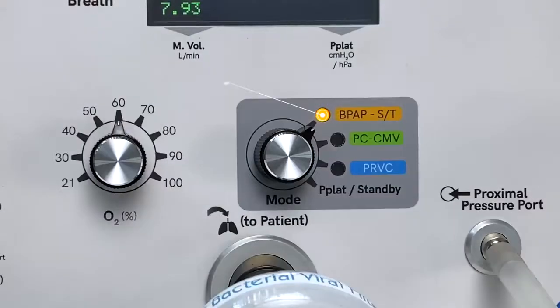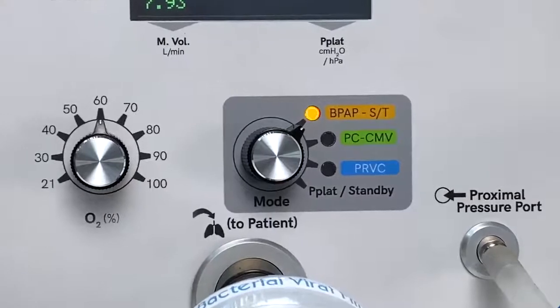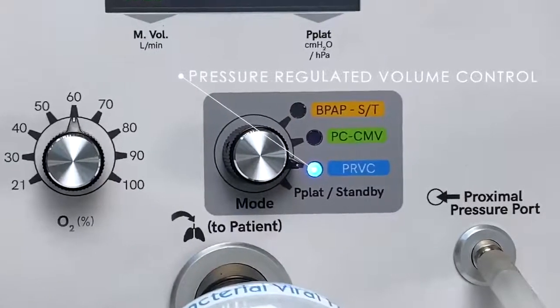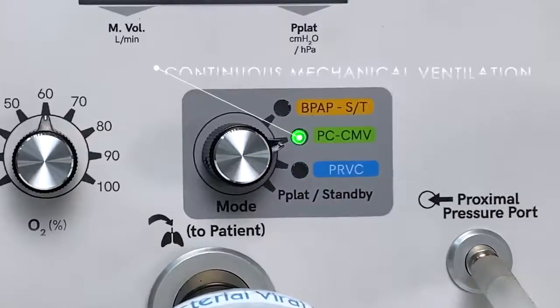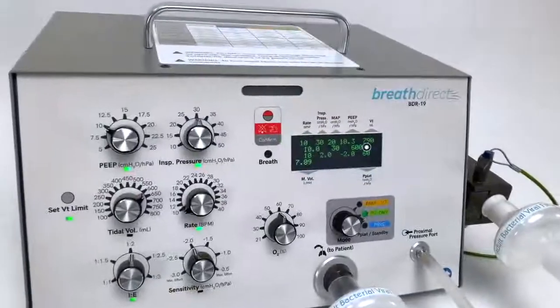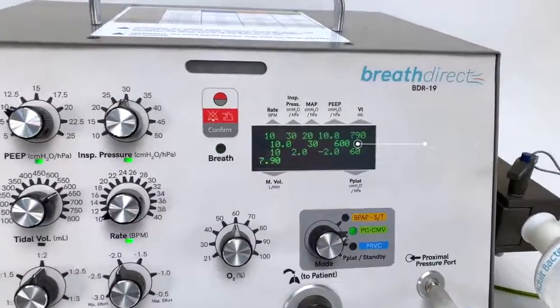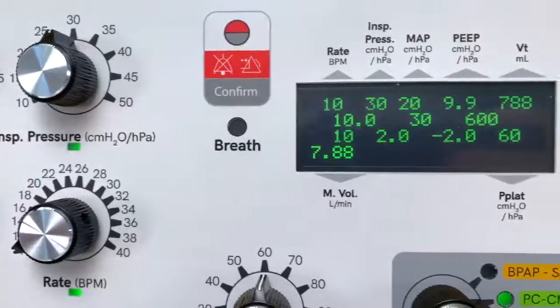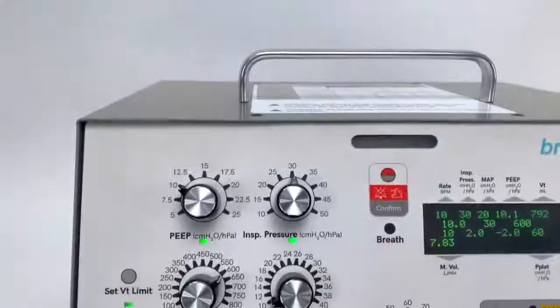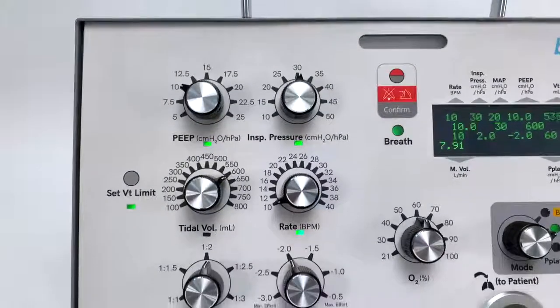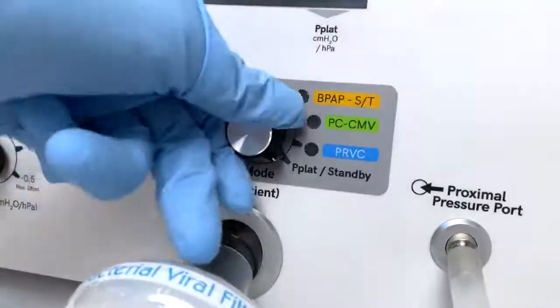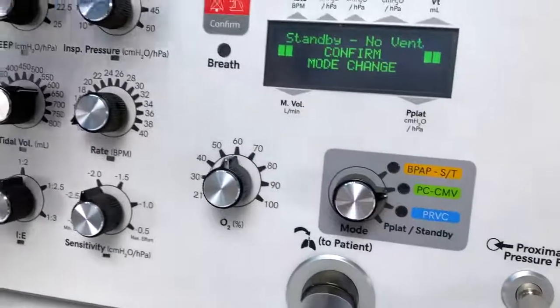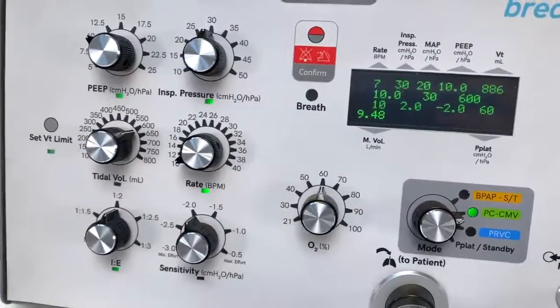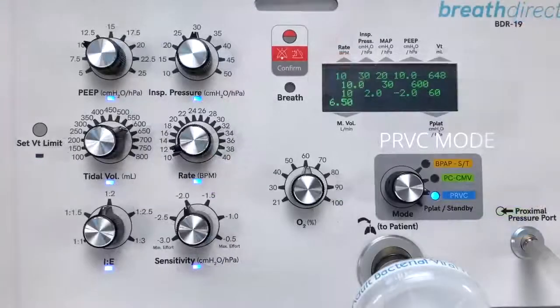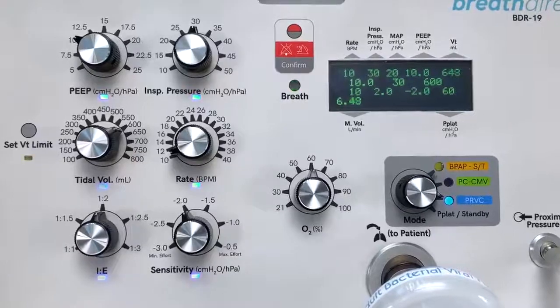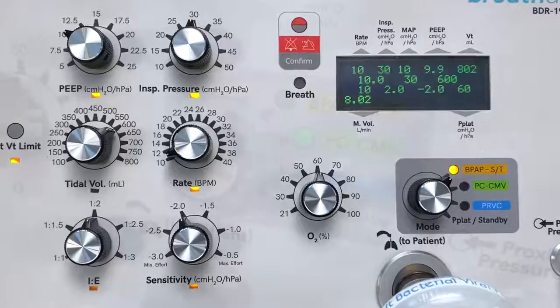These include bilevel positive airway pressure, or BPAP, which includes a backup rate, pressure regulated volume controlled ventilation, or PRVC, and continuous mechanical ventilation, or CMV. The display screen provides real-time information for breath rate, inspiratory pressure, mean airway pressure, PEEP, delivered tidal volume, and minute volume. When selecting a mode, LEDs clearly prompt the user to set the needed controls for that mode. For example, when setting CMV mode, you are prompted to set PEEP, inspiratory pressure, rate, IE ratio, FiO2 setting, and high and low tidal volume alarm limits. Likewise, when selecting the PRVC or BPAP modes, LEDs will guide you on which controls need to be set.